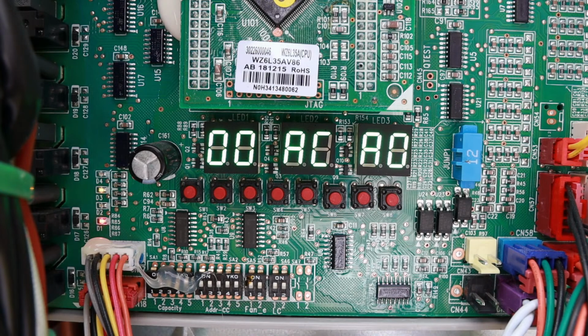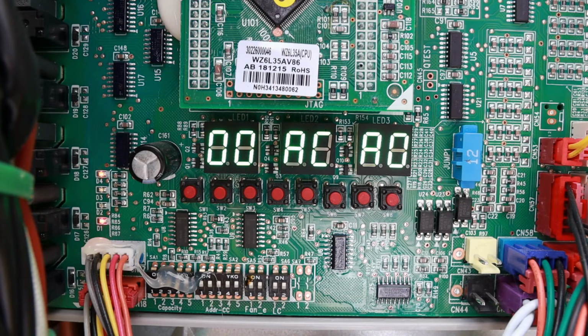When you power up the system for the first time, this is what you're supposed to see on the LEDs: 00 AC A0. A0 means that the system hasn't been commissioned, so now it's time to start the commissioning cycle. Something very important to keep in mind: this A0, you're supposed to see it also on the LEDs of the evaporators, as well as on the LEDs or the display on the controllers. Why? Because we want to see this A0 in every unit so that we know that the whole system is ready to be commissioned. If this A0 is missing from any of the units, you have to go and check what's going on. You have to fix this A0 so that you can proceed to the commissioning cycle. So go back inside and check the units.